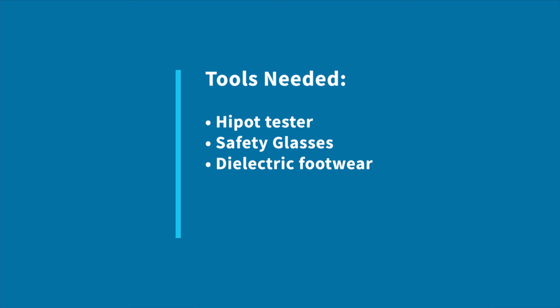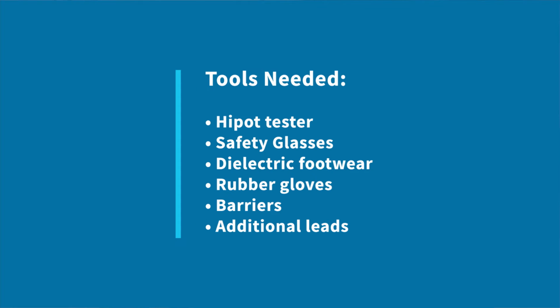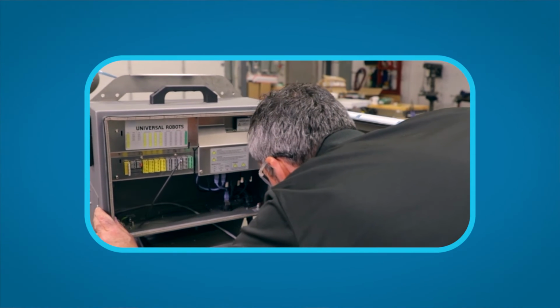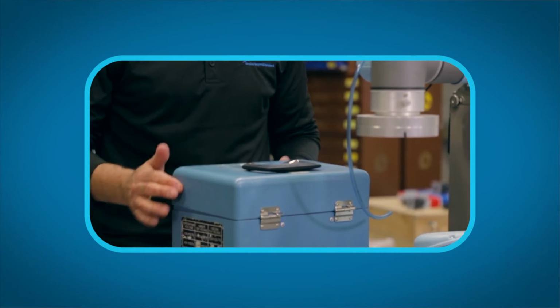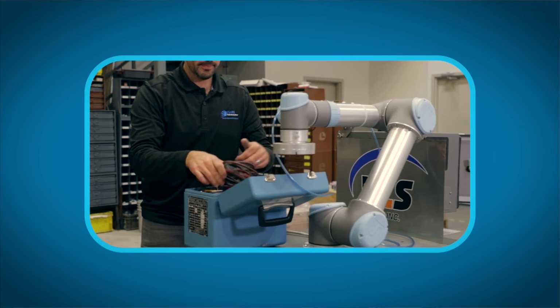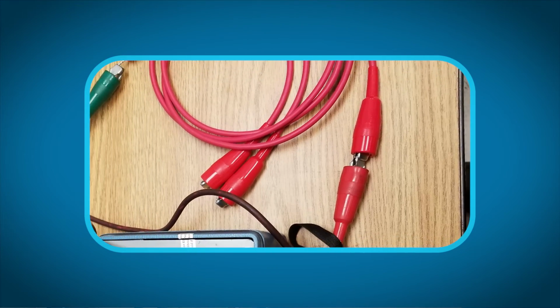Tools needed: HiPot tester, safety glasses, dielectric footwear, rubber gloves, barriers, additional leads. Step 1. Verify that the tester and its cables are in proper working condition. Do this by connecting the leads together and performing a test.